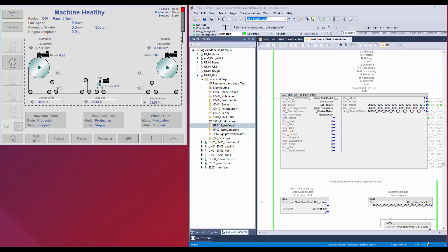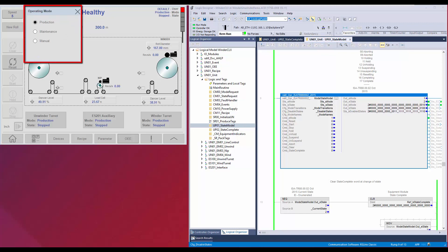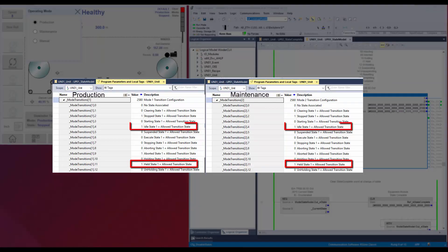Next I will demonstrate the mode change options. The mode change permissions for each state is configurable in the mode transition configuration. In this application, I have three modes: production, maintenance, and manual. In maintenance mode, I have programmed the logic to engage all equipment with the line master similar to production mode. Instead of continuously running the line master, the operator is given control to inch the master when required to do maintenance. Since the axis relations are similar in maintenance and production, I have configured the mode transition to allow mode change between production and maintenance in held and idle state. This saves time and unnecessary resetting of the machine while switching between maintenance and production.